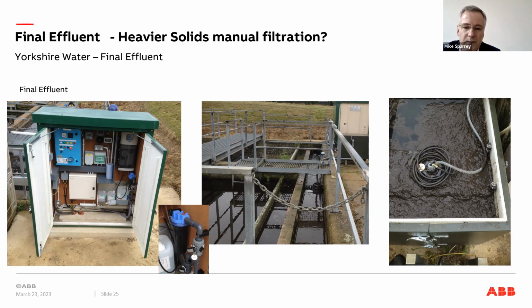If you look at the central picture, you can see the final effluent - where you place the filter or submersible pump was very, very key. The right-hand picture shows it's worth looking at the application carefully - here they were just using a sample pump, not a filter, just extracting the sample. I'd say they got it in the wrong place because there were a lot of solids on top. I would have put that sample pump somewhere else, and probably used a filtration system as the primary source rather than relying on the manual filter, because that was putting extra work onto the instrument.